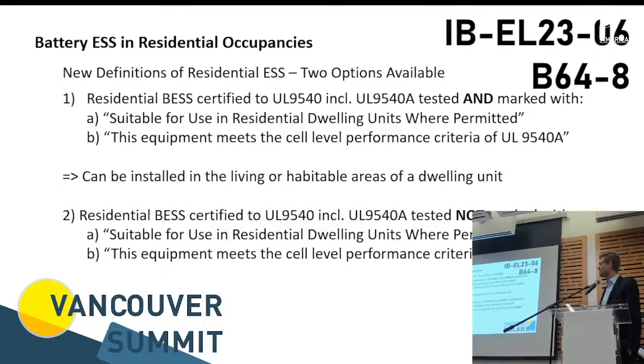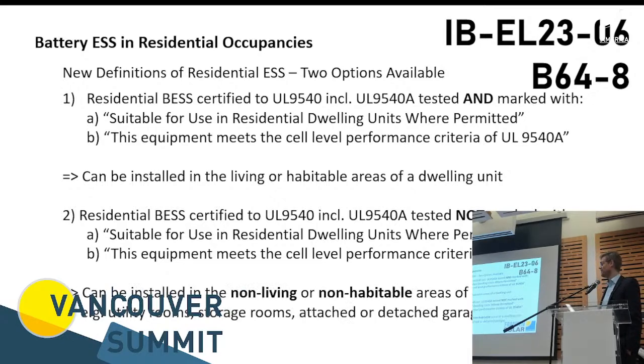to the second option. And if you would have that, you can pretty much install it anywhere. But we don't have that, so we have to go to the second one, where we still have the certification, but we do not have the compliance test for the cell level performance, and we don't have "suitable for use in residential dwellings" on the type label. And then you can install it in the non-living or non-habitable areas of a dwelling. Typically, that's a utility room or the garage, as I mentioned earlier, as the most suitable place for these kinds of systems.